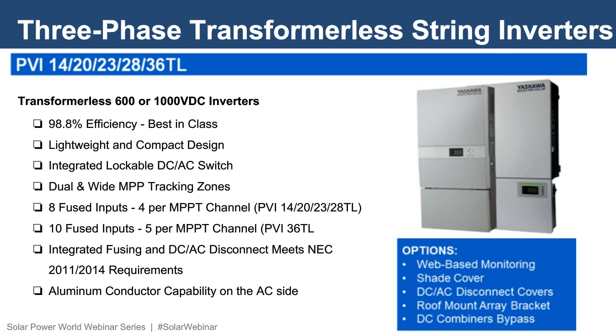These transformerless string inverters have a best-in-class efficiency over 98%. As you see in the picture, they're a lightweight, compact design, very installer-friendly, important when working on rooftops or crowded, preoccupied electrical closets. These units have integrated and lockable DC and AC disconnect switches. This is great as it alleviates the requirement for a separate external or adjacently mounted disconnect switch.